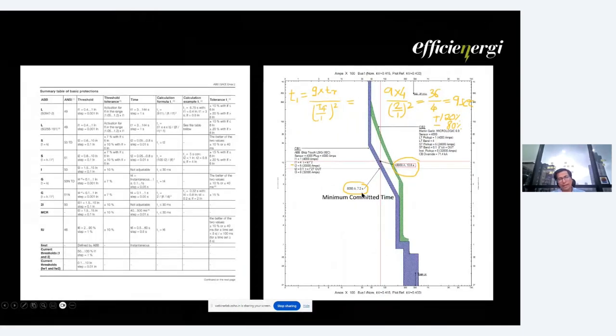So that is where the minimum and maximum tolerances come into play when we have to coordinate series breakers. It is also called the minimum committed time. So 7.2 is the minimum committed time, meaning that for 8000 ampere, this particular protection device will not trip in less than 7.2 seconds. So that is a committed time.